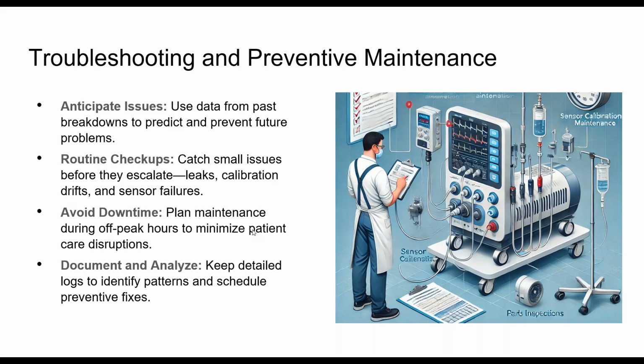An AEM can be doing more than what the manufacturer suggests to enhance the reliability or safety of that device. One thing I will suggest to you is if you do have something critical like a ventilator on an AEM, make sure that you consider at least giving feedback to the manufacturer about the reasons why you have decided that it's better to add some steps. They may actually incorporate that into their next recommendations as a manufacturer.